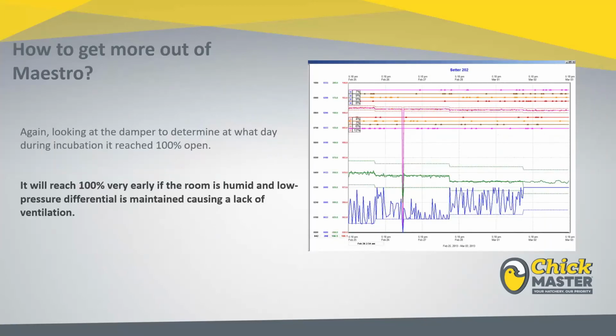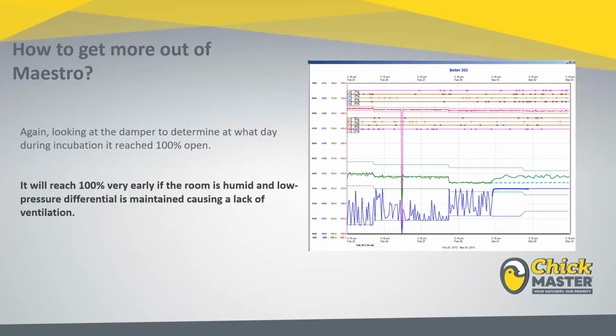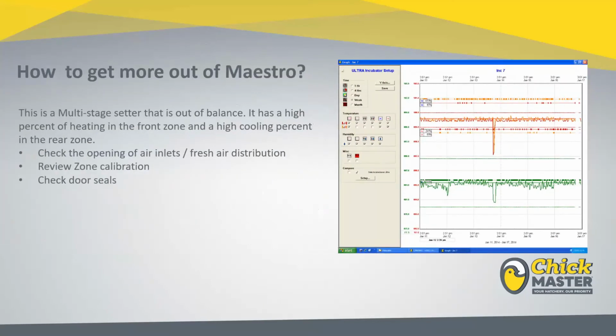The same goes when we look at a machine that works in the opposite direction. So if we have a damper opening that is not, and this is our normal known good graph, when we see one that reaches 100% opening very early and our humidity is consistently above our set point, then oftentimes that's an indicator that we either have really high humidity conditions in the room or maybe a lack of differential pressure across the machine. We're just not getting adequate airflow through the machine. And you can see that in this part of the graph. So again, it's one of those pieces that you can focus on and look into.